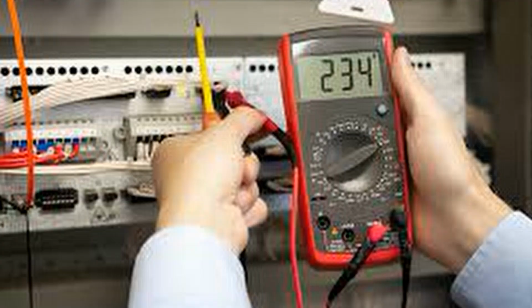You have mandatory 5-yearly electrical tests where the electrician will come around, check all the terminals, and do insulation resistance testing to see if there are any cables that have weak insulation. For example, they've been exposed to so many surges over the years and they're now weak, they are a fire risk and need to be changed. Definitely you need to have surge protection installed as well. So this is what we're talking about, guys. This is the education that I want to give you so that you can make the right move.